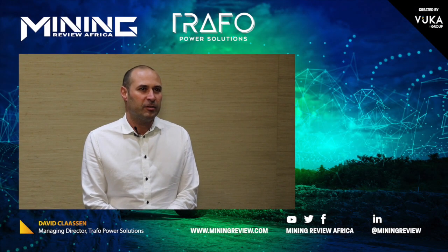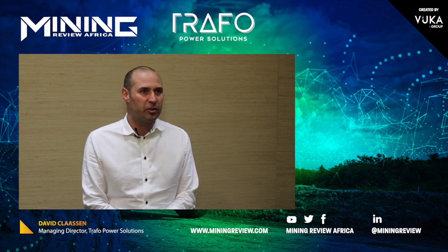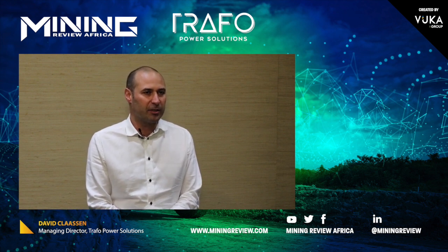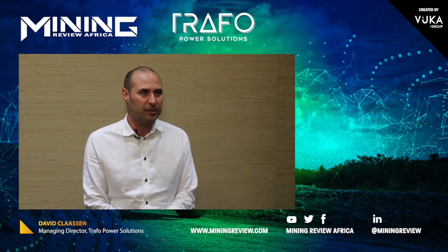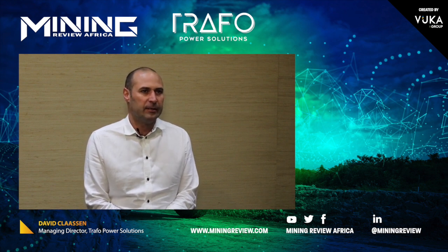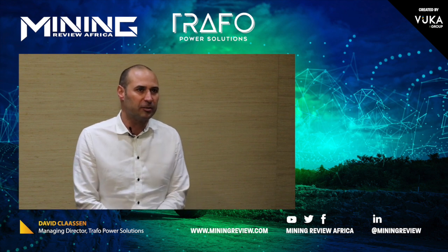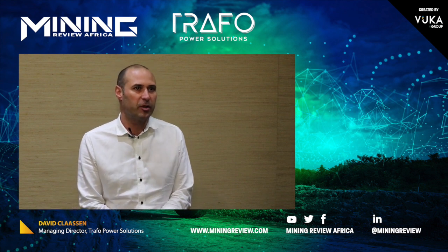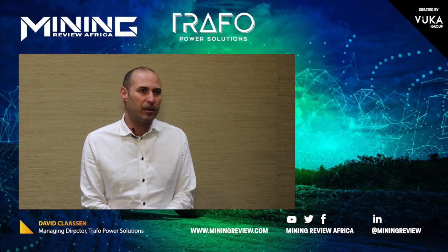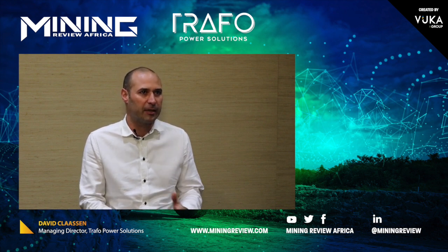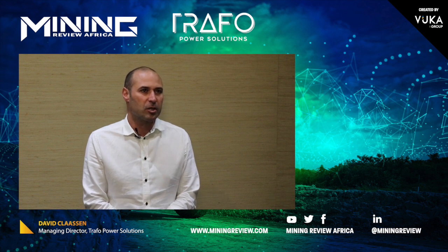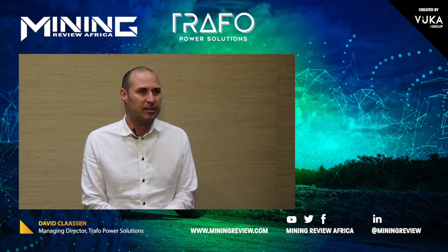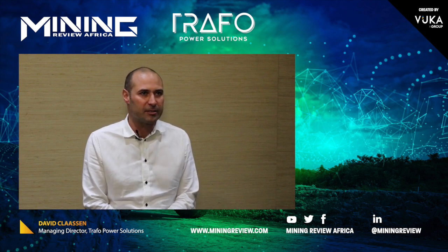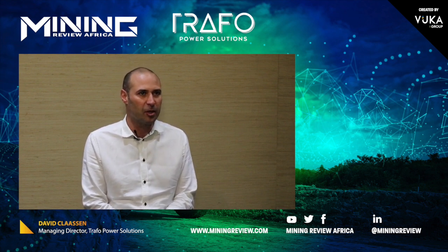You have to define what the harsh conditions are. Generally speaking, in mining applications we have a large amount of dust and often a large amount of water. Dry type transformers have the medium voltage winding completely cast in resin, which is a good design for ingress and for pollution. So the transformer design itself lends itself to those types of applications, as long as they are well protected in the correct IP rated enclosures.